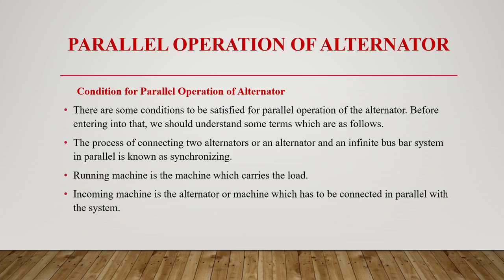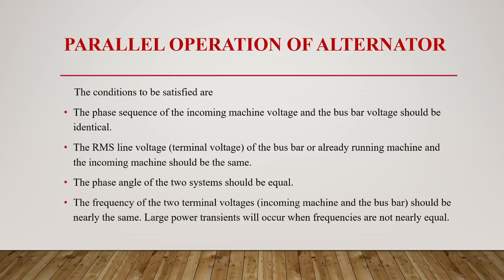The process of connecting two alternators, or an alternator and an infinite bus bar system, in parallel is known as synchronizing. The running machine is the machine which carries the load, and the incoming machine is the alternator or machine which has to be connected in parallel with the system. We have to know these terms: synchronizing, running machine and incoming machine.